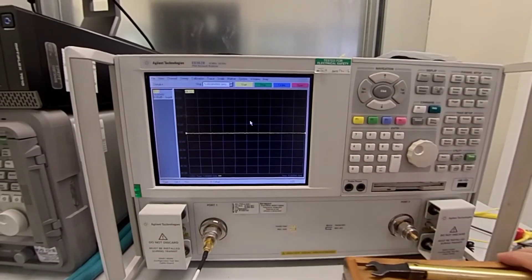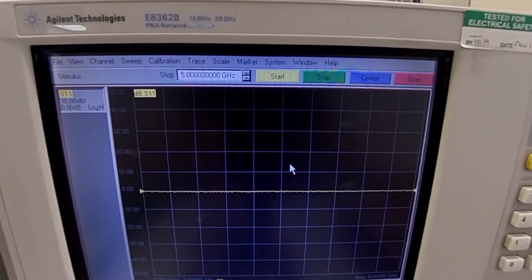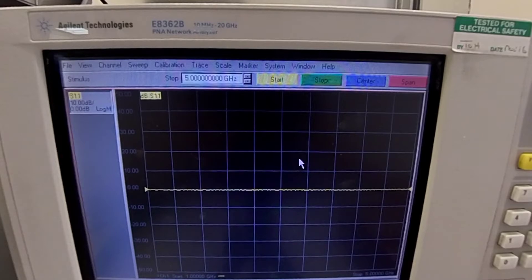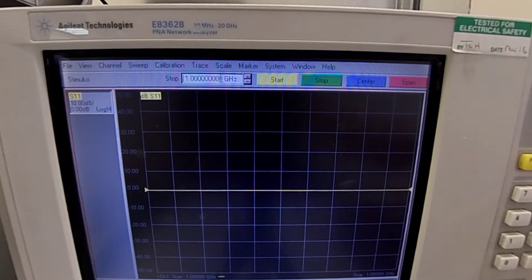Now we will start off with the calibration. The first step of the calibration is to select the desired frequency. In this case we will select 1 GHz as a start frequency. Using the keypad on the right, we will select the stop frequency to 5 GHz.